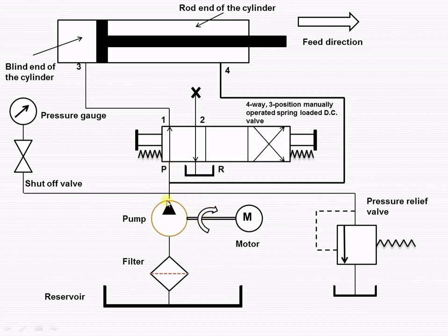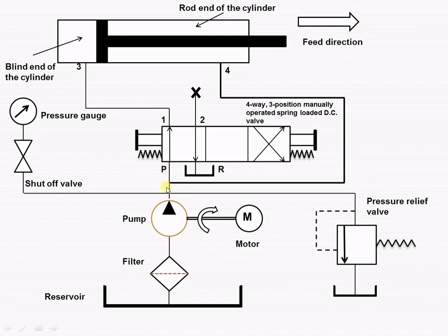When the spool of the four-way direction control valve is in the left envelope mode, the fluid flows from reservoir to filter, filter to pump, pump to port P, P to port 1, then to port 3 and 4, entering the blind end of the cylinder and causing the piston rod to move in the forward direction. Apart from the pump flow, the fluid from the rod end of the cylinder is also added to this flow.